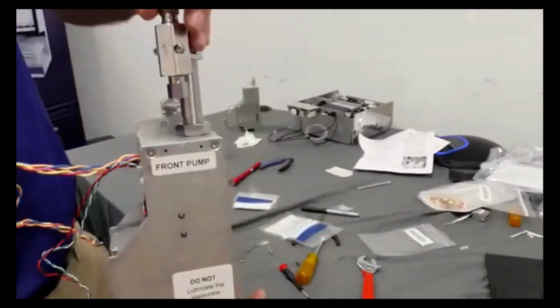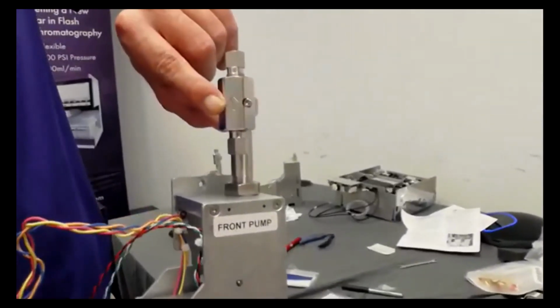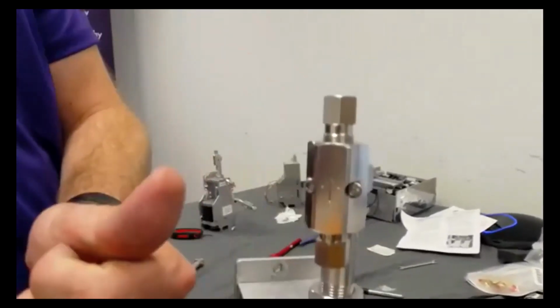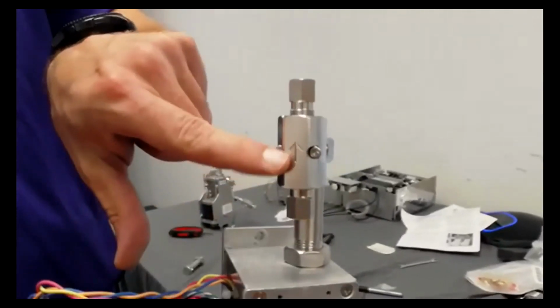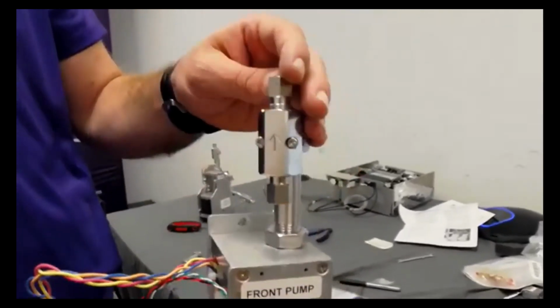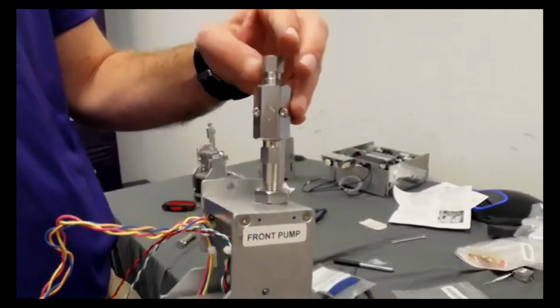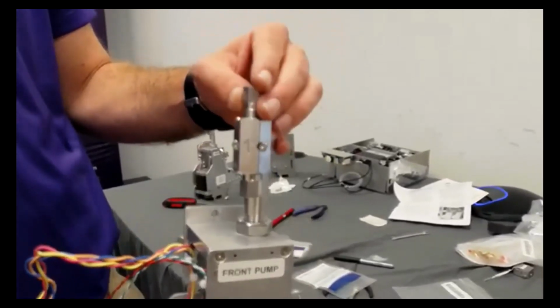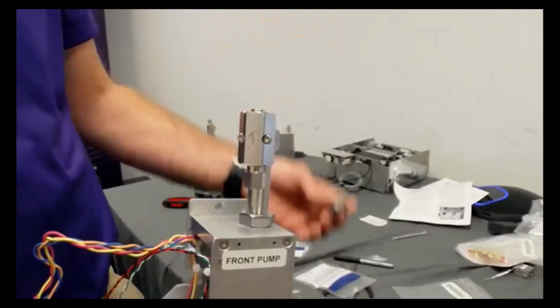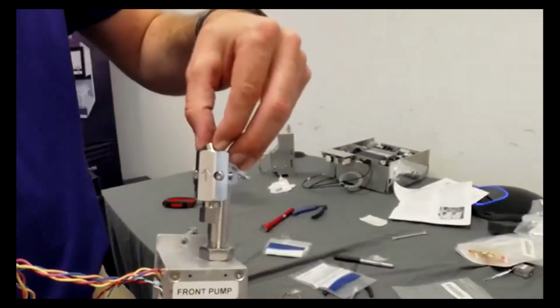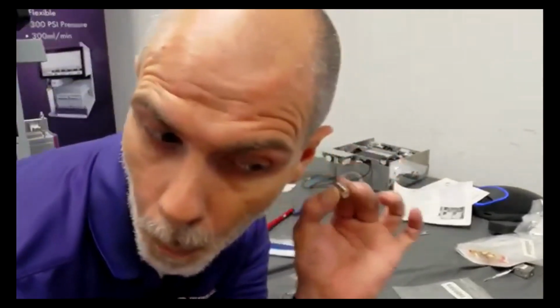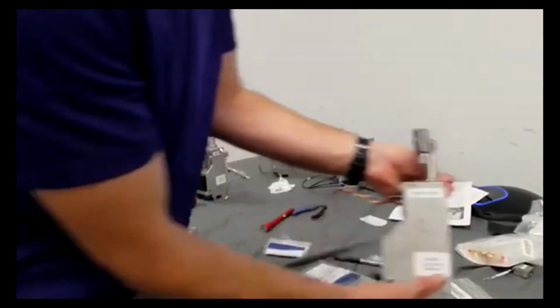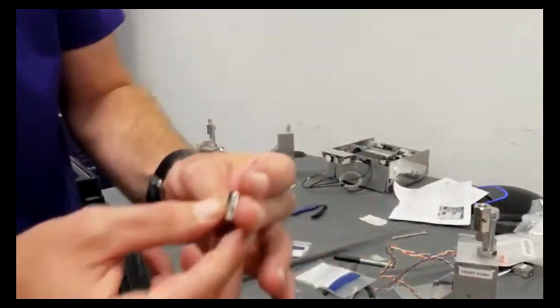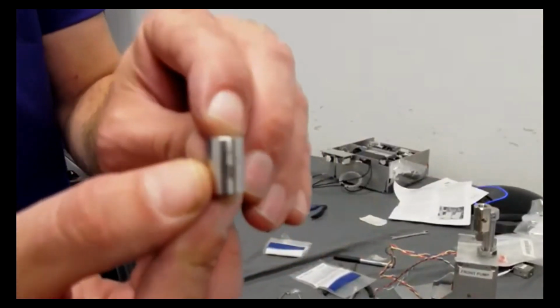Notice the arrow on there. It's always pointing up. This arrow, if it's pointing down, bad. So I'm loosening this up now. And in there is my check valve. It rattles, that's good. Now the check valve itself will have an arrow as well. You kind of see that?